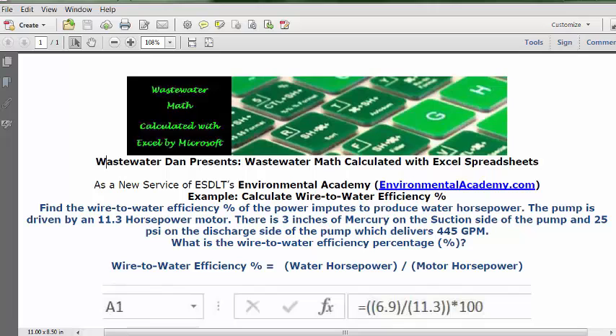What is the wire-to-water efficiency percentage? This solution uses the formula to calculate wire-to-water efficiency percentage, which equals the water horsepower divided by the motor horsepower. You can see we are given the motor horsepower, but we are not given the water horsepower.